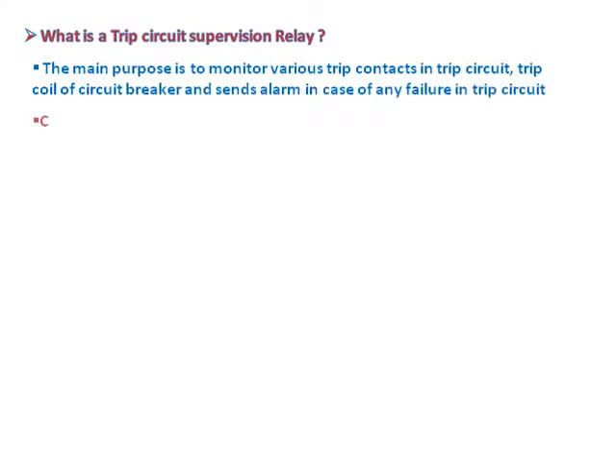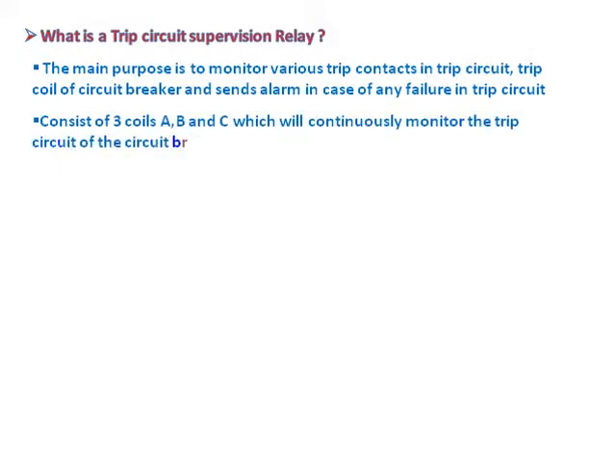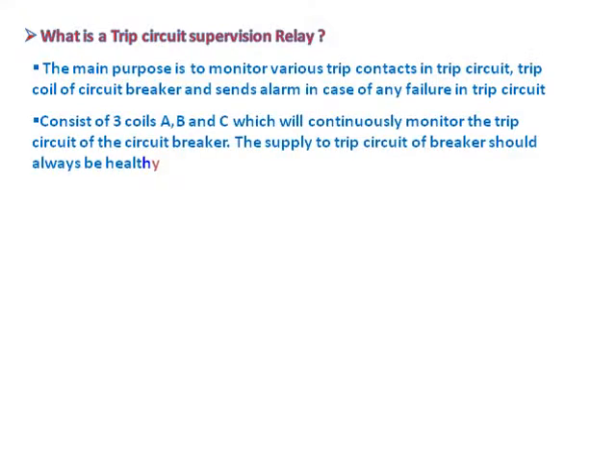It consists of three coils A, B and C, which will continuously monitor the trip circuit of the circuit breaker. The supply to the trip circuit of breakers should always be healthy to trip the circuit breaker in case of any fault.